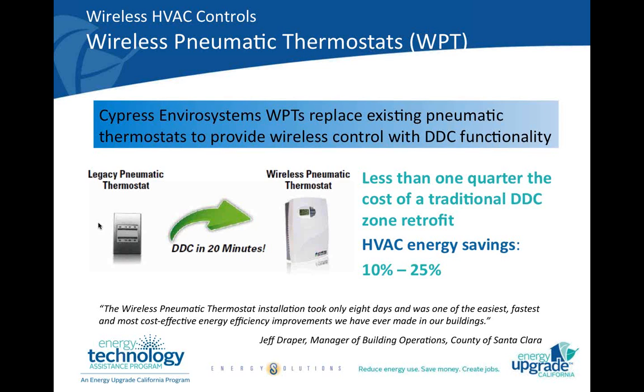The second wireless HVAC technology that ETAP supports is the wireless pneumatic thermostat, which is made by Cypress Envirosystems. The idea behind a wireless pneumatic thermostat is that it is a direct replacement for an existing pneumatic thermostat, but it provides wireless control and allows DDC-like functionality. Similar to DART, it's a fraction of the cost of a traditional DDC retrofit, which is going to require a lot of wiring, etc. And it can also give you significant HVAC energy savings depending on the way that it's used.